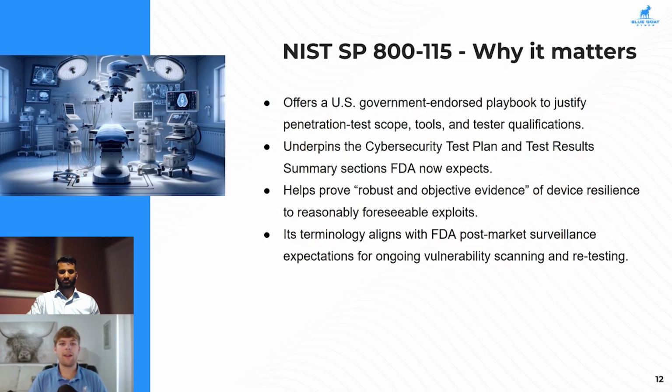Now, why does it matter? This is an endorsed playbook that justifies the pen test scope, tools, and qualification. So this talks about what the process should look like, how we cover test planning, how we address our test cases. All of this is required by the FDA for a pre-market submission. And in addition to requiring it in this specific format, all of this testing in general is required. Penetration testing is getting pushed to be done by third-party reviewers. And so that's going to be getting your testing done by a sufficiently skilled penetration testing firm outside of your organization.